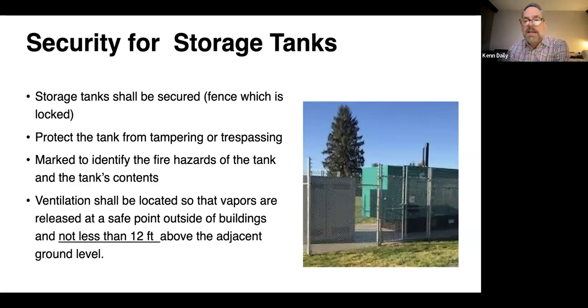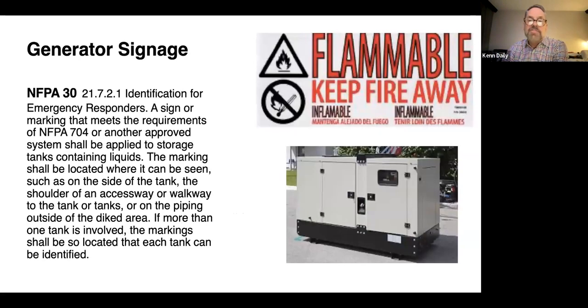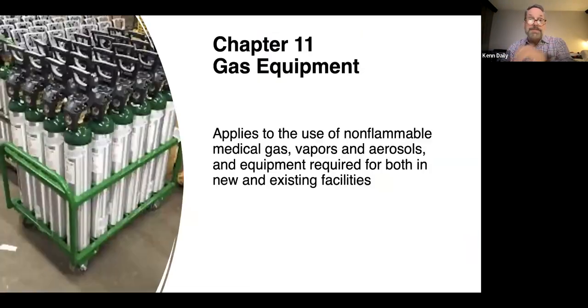And then in addition to the protection of fuel, diesel fuel has to also have a 12-foot vent stack. So from the ground, the top of the vent stack must be no less than 12 feet to exhaust the burning of diesel fuel. Signage on diesel tanks or any tanks, period. Flammable, keep away from fire, so there should be no smoking near generators and their fuel source.